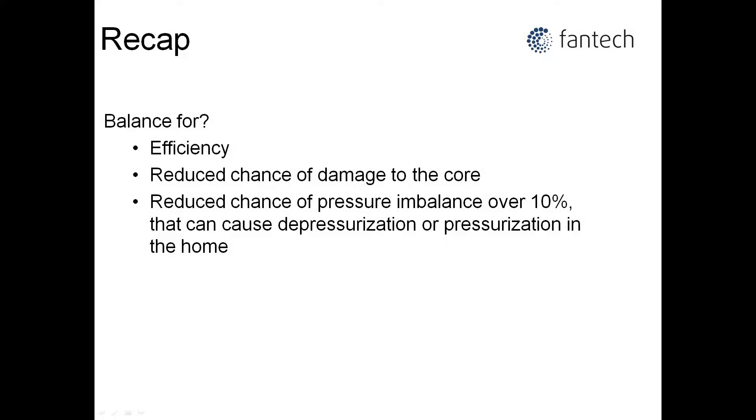To recap, a HRV or ERV works best and is most efficient when the air flows are equal. In areas where freezing occurs, a balanced system stands less chance of freezing up. It also does not depressurize the home causing backdrafting of fossil fuel appliances or open fires, or pressurizing the home forcing moisture into the structure causing damage and possible mold growth. It is recommended that balancing be done by a licensed HVAC contractor as they have the tools to do the job.